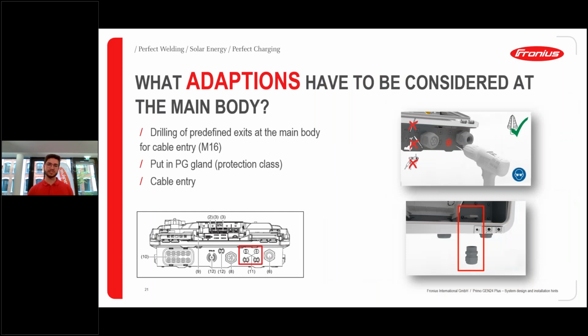Okay, one last slide for the PV point is the adaptations we have to make on the main body. There is no cable gland for the PV point pre-installed, because not every customer uses it, of course. And if the customer wants to use it, you have to pre-drill it. Like we can see here in the picture, there are predefined positions, like exits, on the main body that you can pre-drill, and then you have to set your own PG gland here for the protection class where you can cable the PV point. This is for the cable entry and to make sure that the IP66 class is still intact. So this is the only adaptation we need to make when doing a PV point.